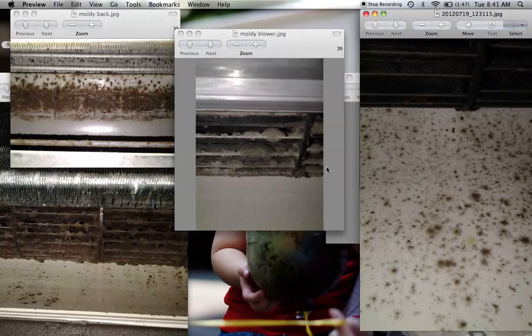Another aspect of why you should clean it up properly is that if you take out the big chunk, you leave a small little mold particle down there. Without totally wiping it out, it grows back. So come to think about it, in the first year of new aircon installation, it lasts you 1 good year. Why is it that in the subsequent years, after you do general servicing, it seems to come back more often, every 3 months, every 6 months? The reason is because it's not been totally wiped out. It grows back. So if you clean it up properly, then it reinstates the aircon back to factory condition.